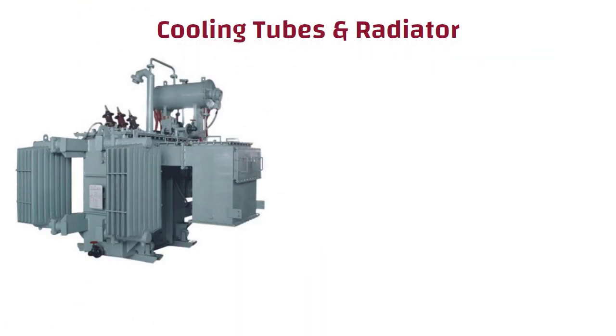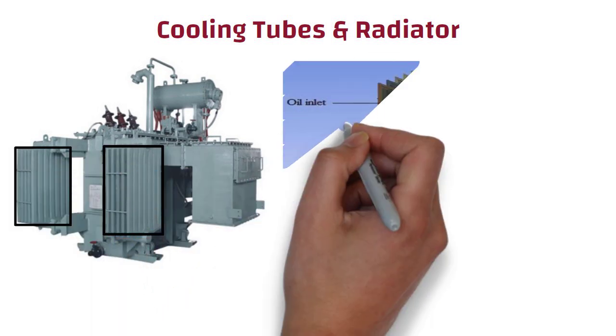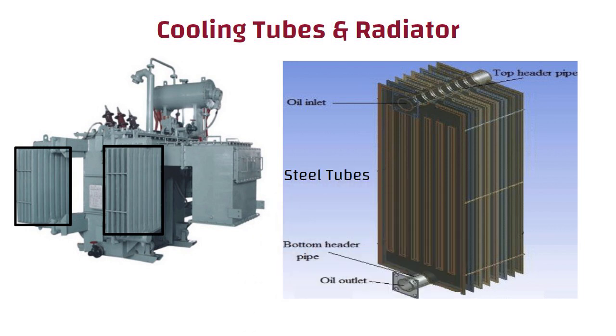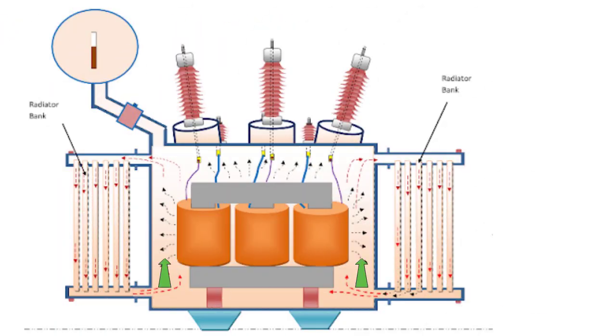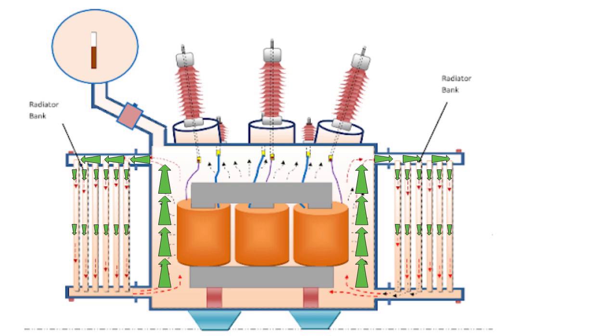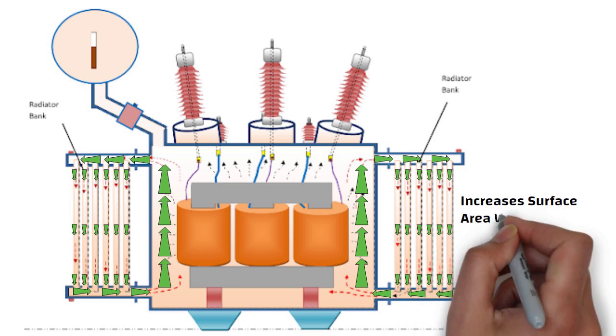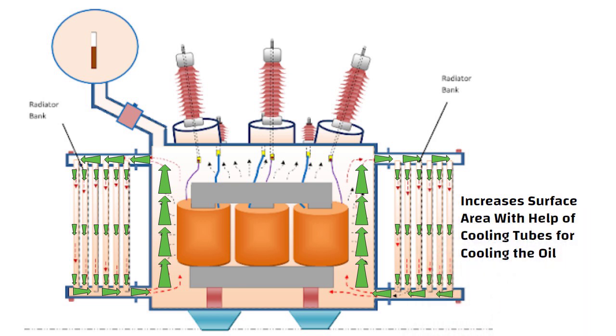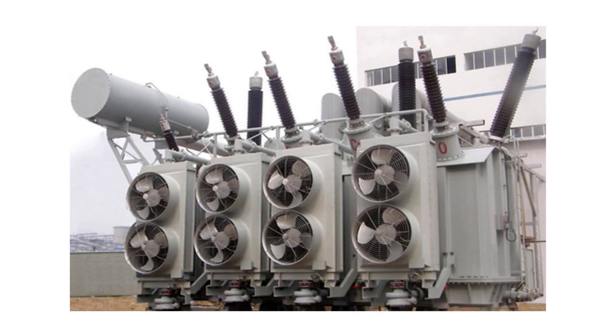Now let us understand cooling tubes and the radiator. You can see in this picture, this is the radiator. The radiator consists of very thin steel tubes. The warm oil increases in volume and comes to the upper portion of the main tank. Then this oil enters the top portion of the radiator, comes down through these thin tubes and comes back to the main tank through the bottom portion of the radiator. This cycle repeats continuously. The radiator just increases the surface area with the help of cooling tubes for cooling the oil. This cooling can be accelerated further by forced air provided by means of a fan.